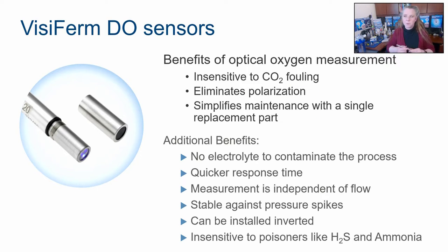So why do people really care about optical oxygen? Why has there been this huge push to move away from polarographic? Well, there's no electrolyte in this. That means you don't have to worry about the CO2 fouling that you find in polarographic probes. Remember we talked about CO2 going across the membrane, changing the electrolyte strength? Doesn't happen, no electrolyte. No polarization. I can literally calibrate this, plug it in, and take measurements immediately, no downtime. And the entire maintenance of this probe, unlike the whole rinse it, buff it, polish it, refill it, check it, double check it, do it again.